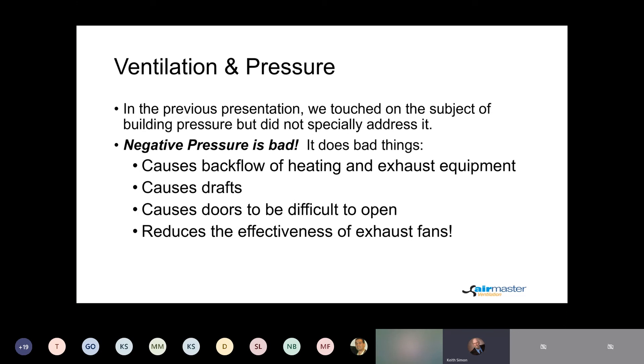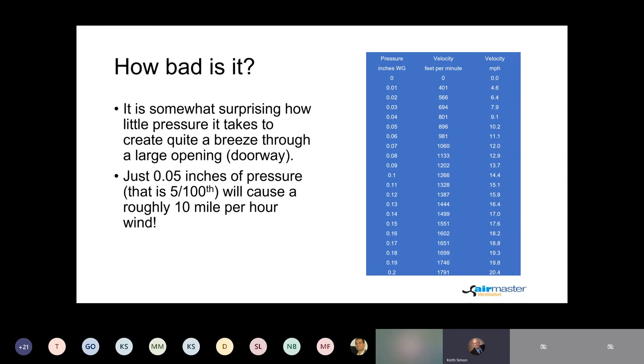This is a negative pressure problem. By my estimate, probably 60% of manufacturing buildings in the US have this problem, particularly in the colder months. I know of a building in Clark Lake, Michigan that has that problem occasionally. And while annoying and potentially a bit dangerous, doorways are not the only symptom of negative pressure. Perhaps more serious is backflow of exhaust gases from combustion equipment, which can put bad stuff into your building and also makes exhaust fans less effective.